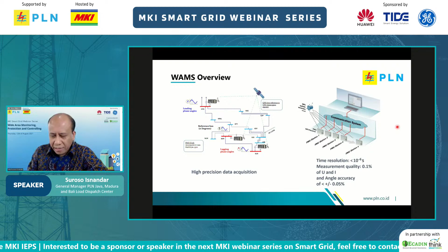In the Indonesian grid code number 20, year 2020, the regulator mandates that system operators must install WAMPAC equipment in substations or power plants, under connection code 4.7. They have also mandated that special telecommunication facilities for operation technology functions such as WAMPAC and PMU must be separated from the SCADA network and from IT functions, as stipulated under connection code 4.12. Also, from appendix CCA 1, 3, 2, 3, and 10, this PMU application should support the long-term WAMPAC vision, be accessible remotely by system operators, and be integrated with a WAMPAC server installed in the control center.